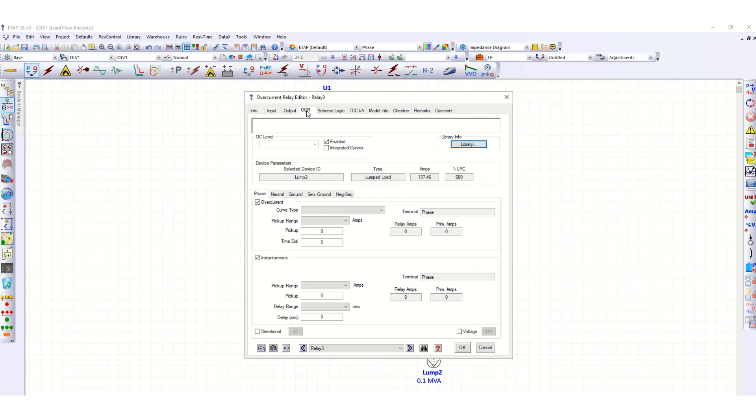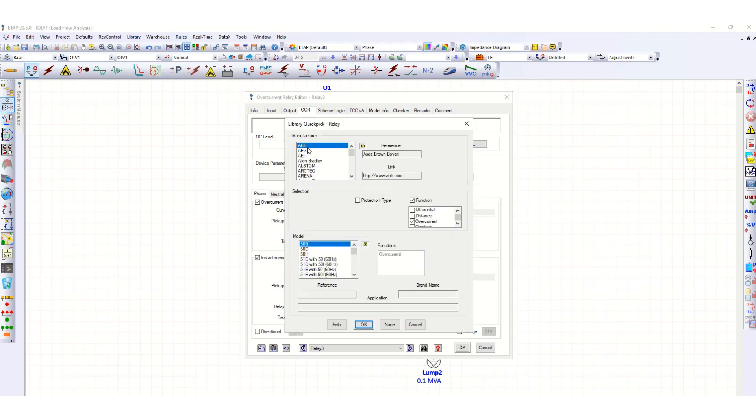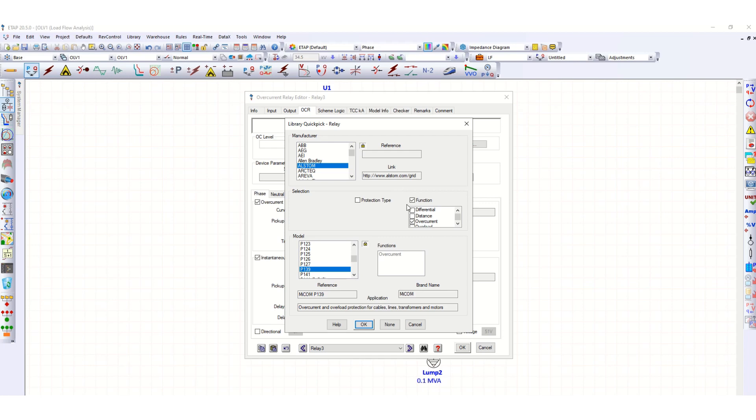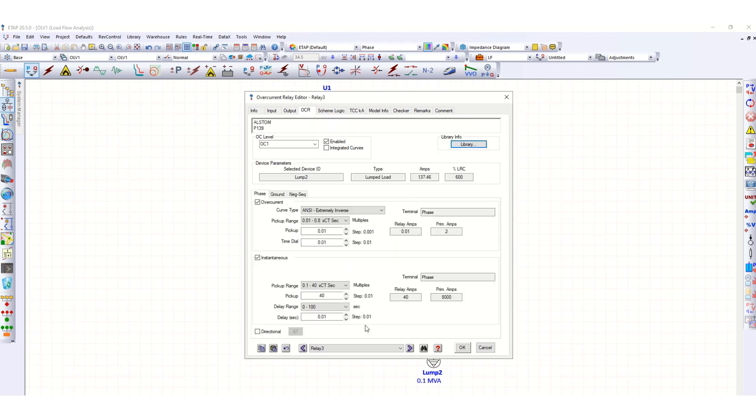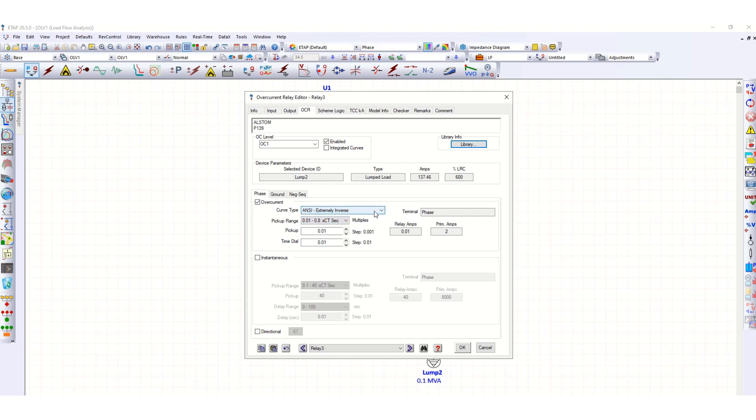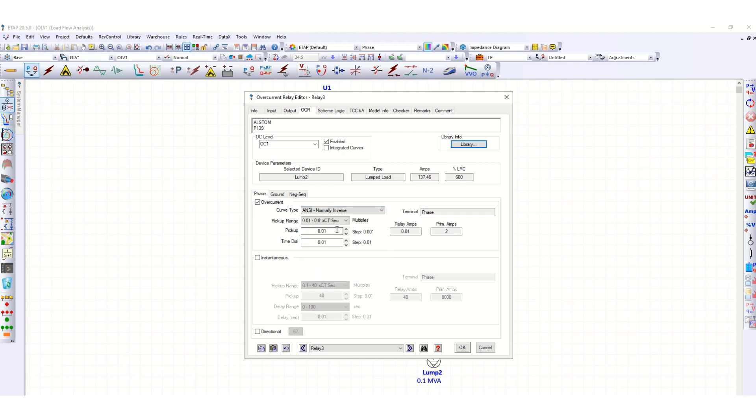For the OCR, let's select the characteristic from library, ETAP library. Suppose this is Alstom's P139 relay for overcurrent and overload protection for cable lines, transformers and motors. Here uncheck this, only the overcurrent element we are considering. Suppose normal inverse, let's select this rating.